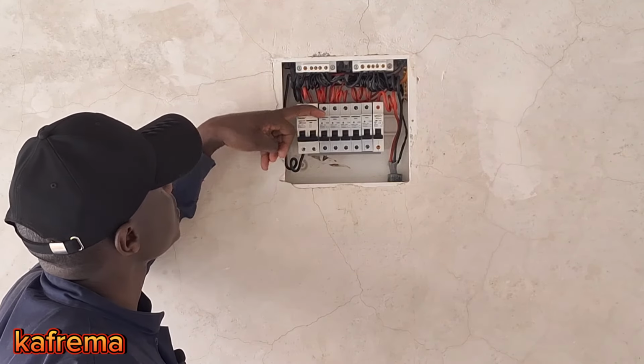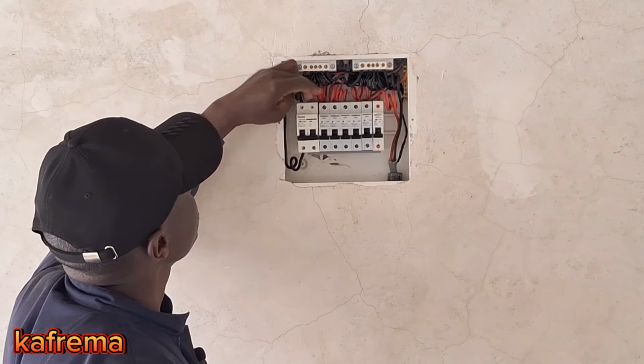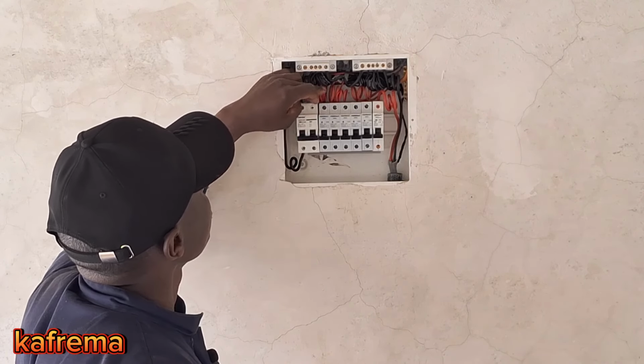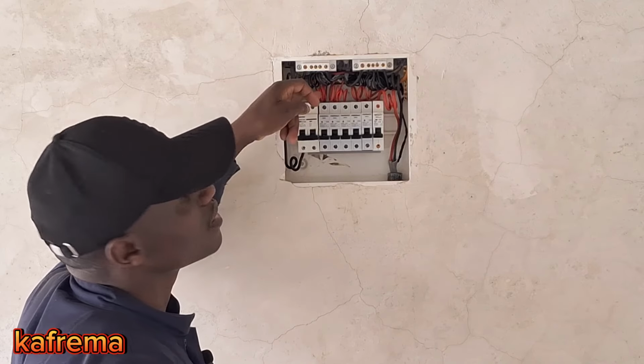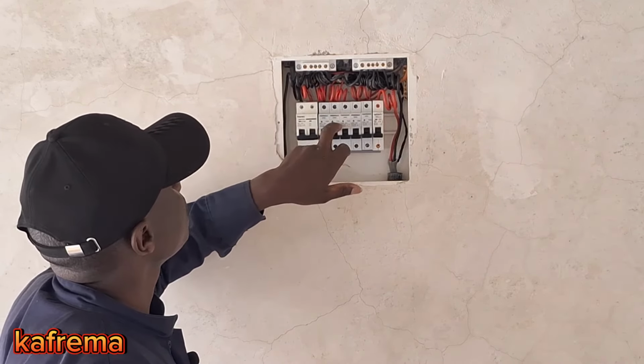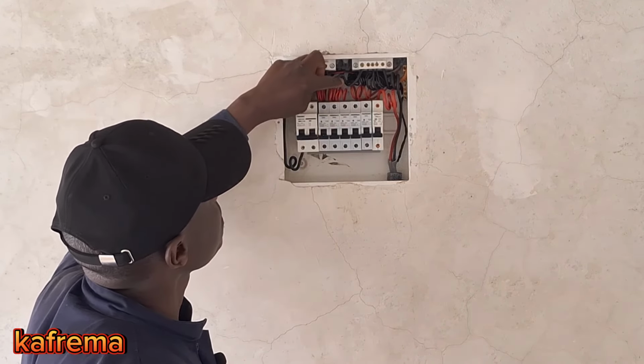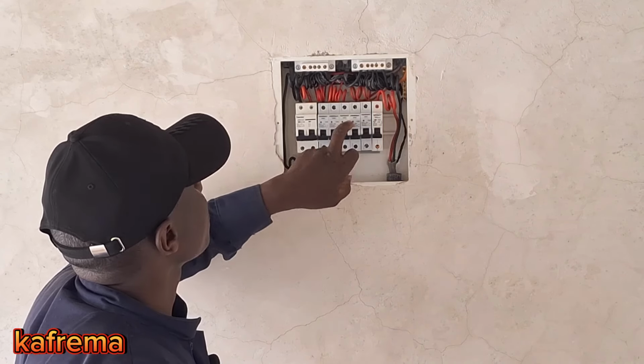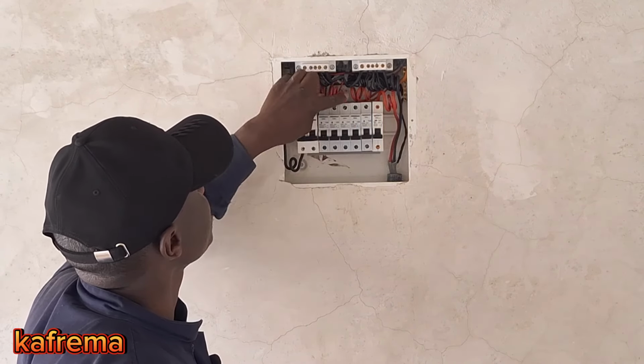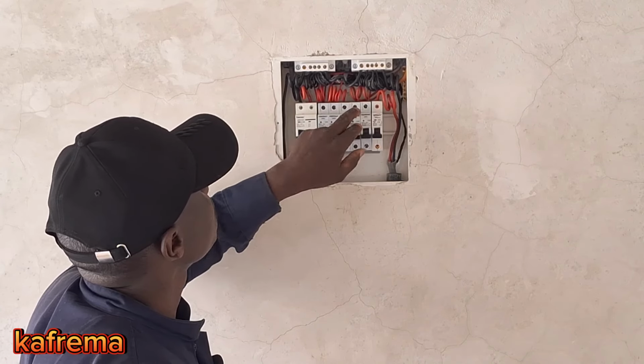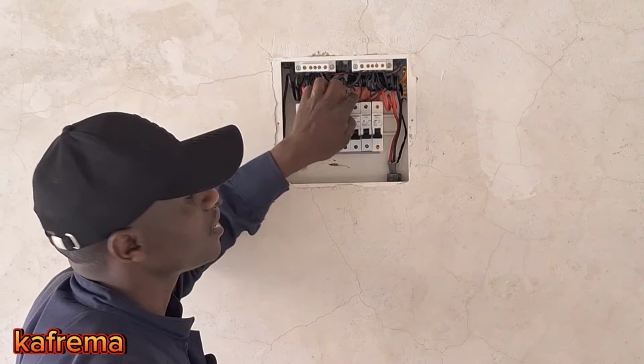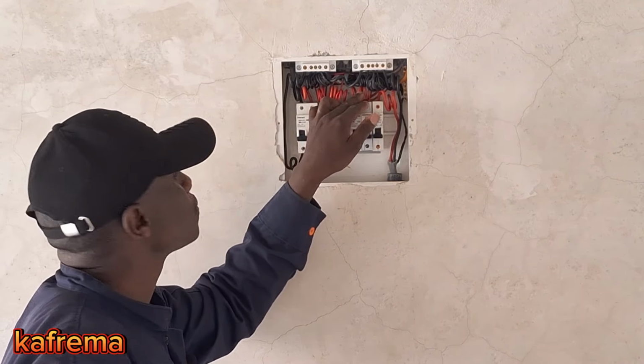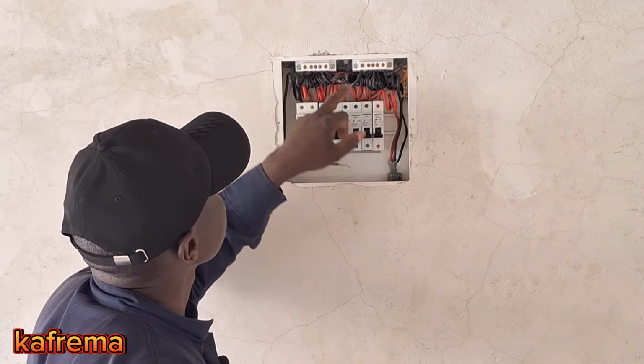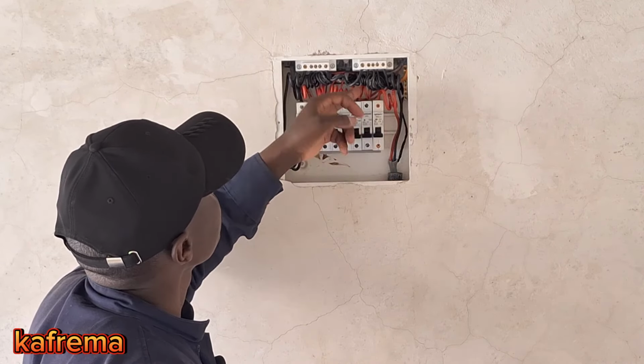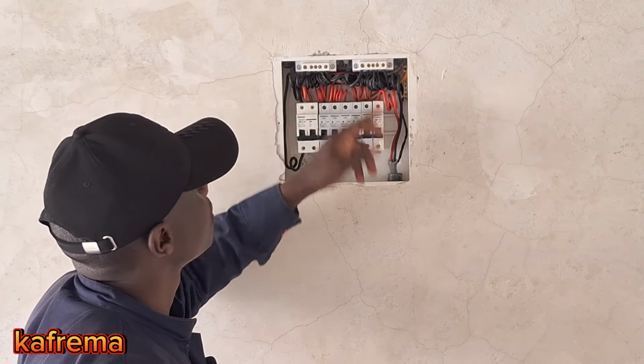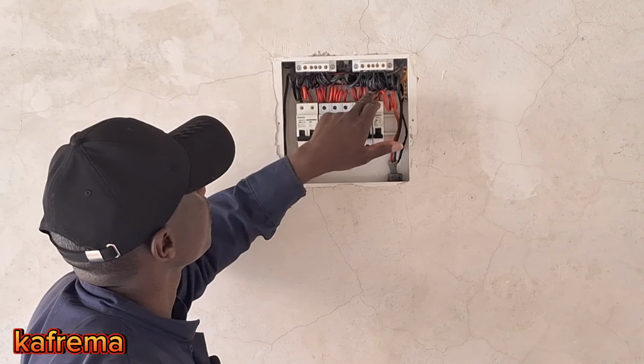Like the first one is a 16, it's serving 16 amperes, it's serving the light. The second one, 20 amperes, serves the socket. The third one is 16, 32. These are heavier. These are inductive motor loads, that is a water pump; the 32 amperes circuit breaker will serve the pump. We have a 16, another one.